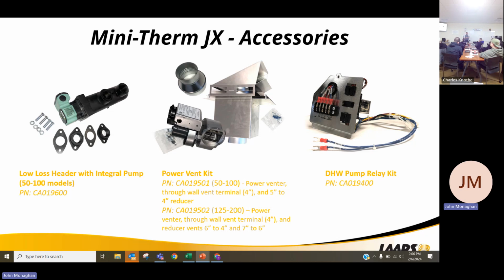And all that's doing is basically doing primary secondary piping for you, making sure that boiler has its proper flow and that we're not getting it shocked with super cold water. Again, we're not doing primary secondary piping on these products because they're high efficiency. We're doing primary secondary piping because they're low mass. Same thing with these products. We're not doing it because they're high efficiency. We're doing it because there's low mass. There's not enough water in that heat exchanger.